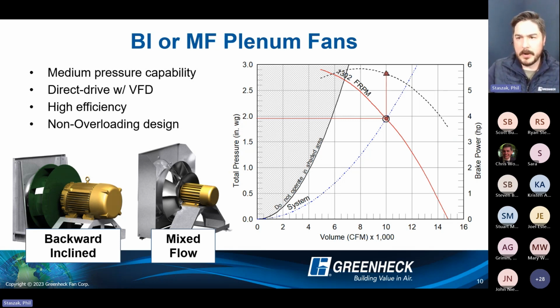Now we follow that brake horsepower line. We were at 8 horsepower just as a standard design. The huge benefit of this fan type already is now we're moving significantly less brake horsepower at the same design with this fan type. So you're just under 6, so you can confidently lay out a 7.5 horsepower motor where you were forced to a 10 horsepower motor right out of the gate with that belt-driven fan option.